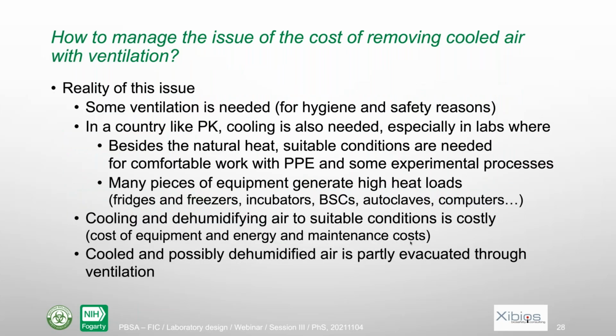It's a real issue and a very important issue with respect to cost and sustainability. Some ventilation is needed, it's very clear, and you saw that during the first sessions. And in a country like Pakistan, cooling is also needed. In addition to the natural heat produced by climate, you also have many pieces of equipment in the lab that generate high heat loads, like fridges, freezers, incubators, biosafety cabinets, autoclaves, computers, and so on. So you need both ventilation and cooling.